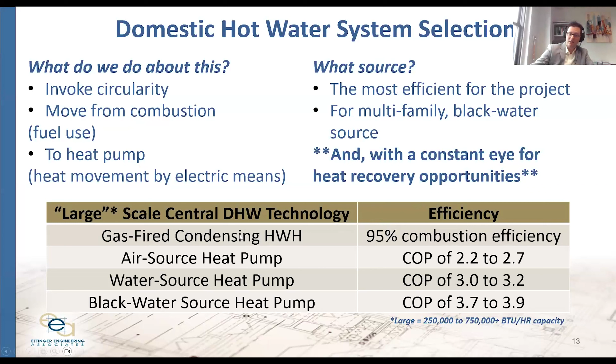Let's ask why the efficiency for blackwater source heat pumps is so much higher than water source and air source. Focus on this blackwater box on the bottom left. Heat pumps thrive with a consistent source temperature. We've heard the buzzword cold climate air source heat pumps — the PTACs of old couldn't run a heat pump cycle at frigid temperatures because the technology wasn't there, so the COP, or heating efficiency, of an air source PTAC falls — the old ones a lot, the new ones a hefty amount.